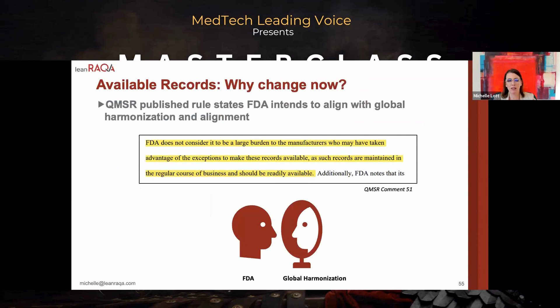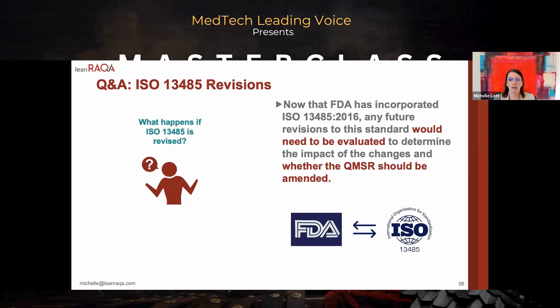So what happens if ISO 13485 is revised? Now that FDA has incorporated ISO 13485, they specifically said that any future changes would not be automatically adopted, but would have to be evaluated in and of themselves to make sure whether or not the QMSR should be amended. So what does this mean for our harmonization? Well, here we are now. We finally, the parallel lines came together, but it means that every 3 years they look at ISO to decide if they need to revise it or not. So it means that this could very easily get deharmonized, just as long as it takes quicker than it took to get harmonized.